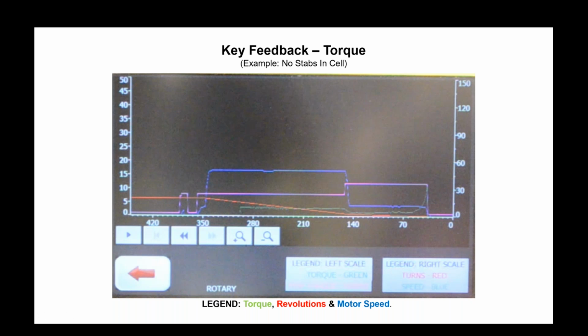One of the other things that's not completely intuitive or obvious as a benefit: if you're racking a breaker and this green torque line just goes to zero, well, maybe the connection to the breaker has become compromised in some way. I've actually been on demonstrations where that's happened. You can see this actual torque graph is everything within probably half a foot-pound, depending on where it's at in the racking sequence. It's a pretty well maintained breaker, it doesn't have any big spikes in the middle of the racking screw where they shouldn't be.